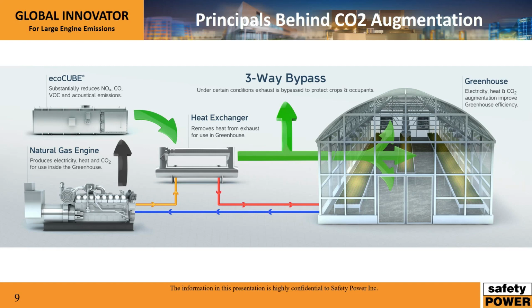As mentioned, the exhaust would typically be transported through a damper valve located in the stack. When the valve is opened, a blower is also engaged for 2 purposes. One, to dilute the CO2 gas, which would usually be in very high concentration, and also to help distribute it through the greenhouse. The CO2 set point is generally measured in the greenhouse, and if the set point is reached, the valve is closed. If the reading is below the set point, the valve is opened.